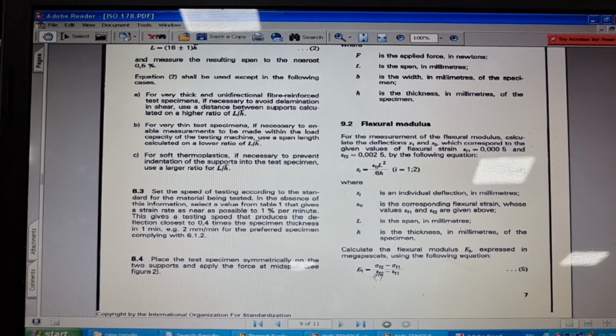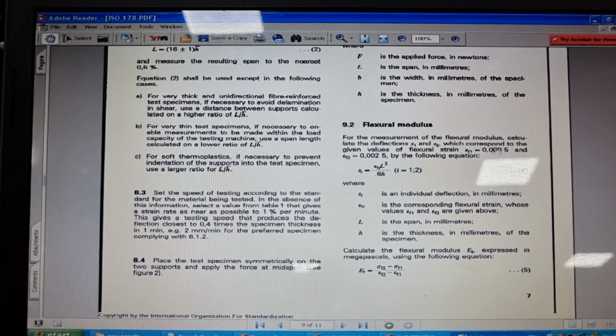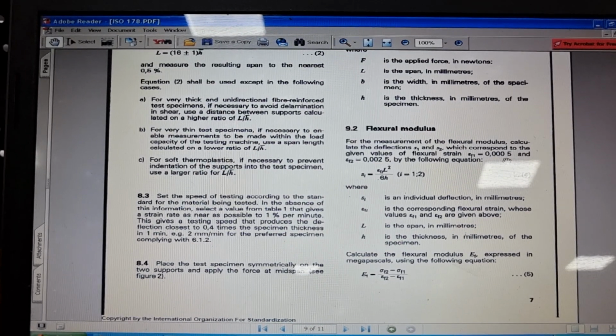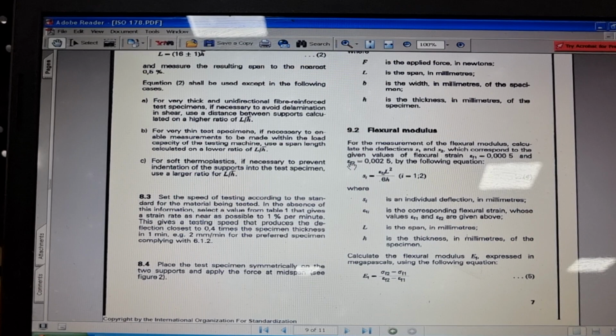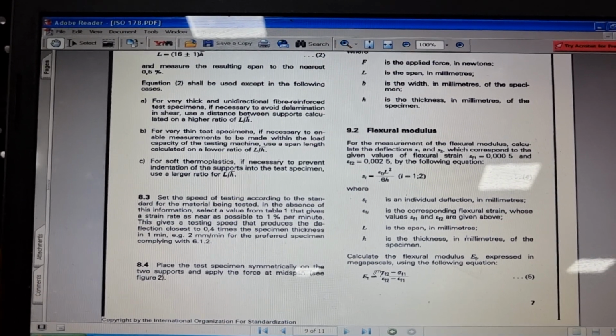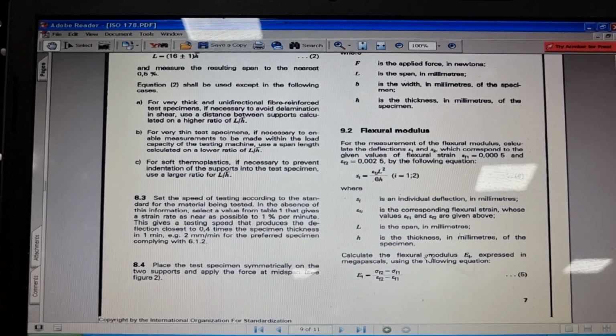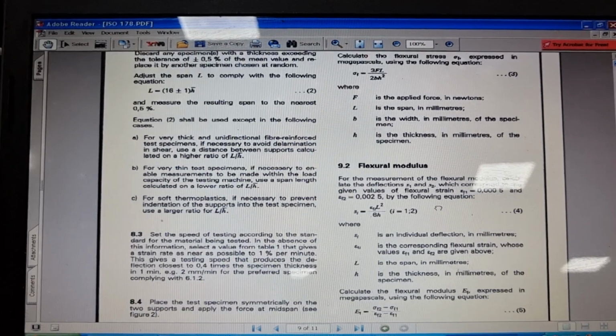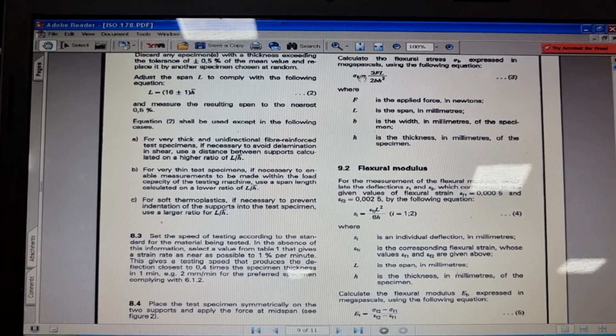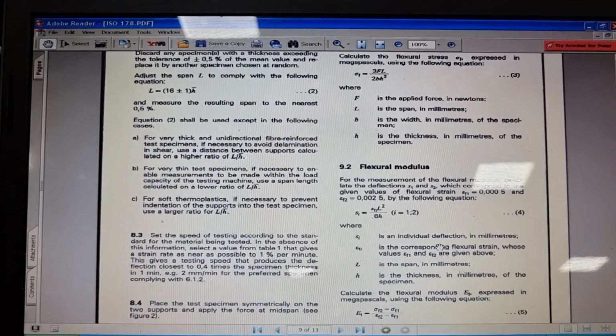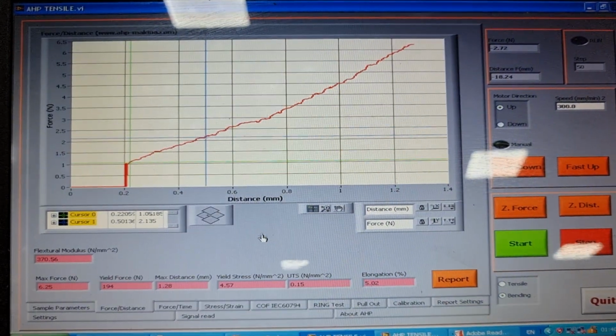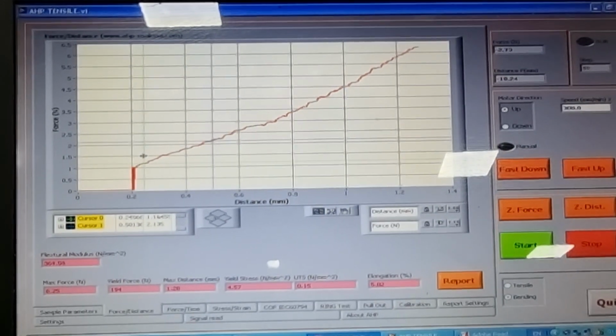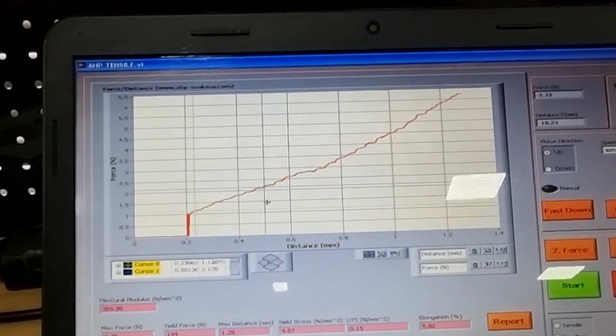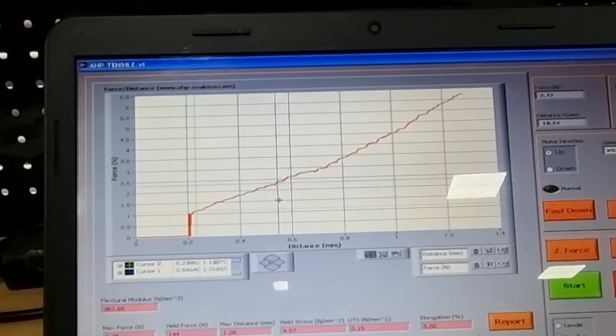Epsilon 1 and epsilon 2 are the two values here, relating to this value of the strain, and the strain of the second point is here. Sigma F2 and sigma F1 are the flexural stresses related to those two displacement points using this formula. This one is flexural stress. The software is working based on this formula. It's easy. You can also use it for any two points of displacement. It can also calculate the flexural modulus between two cursors that you define on the flexural graph.